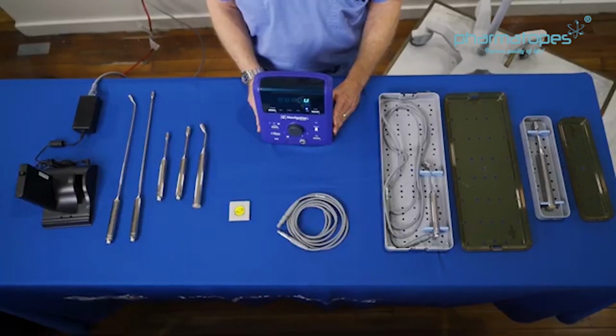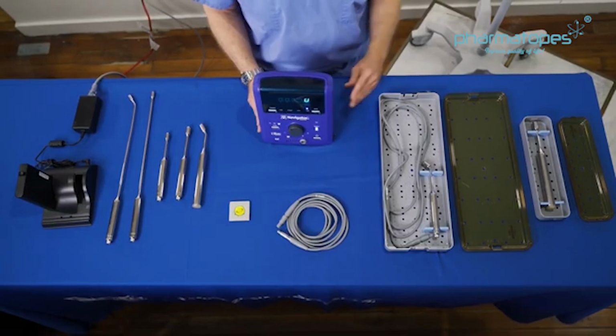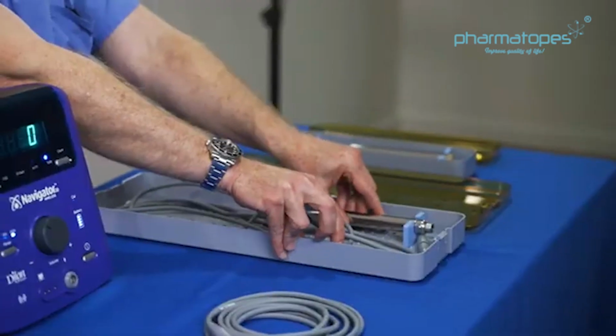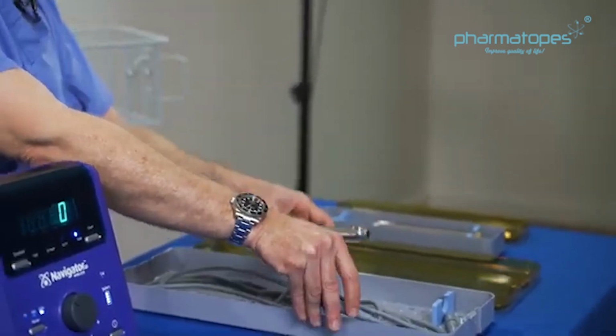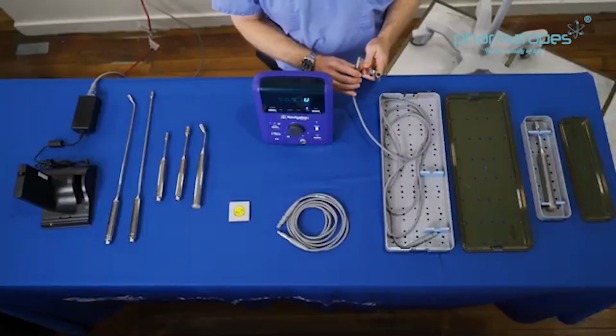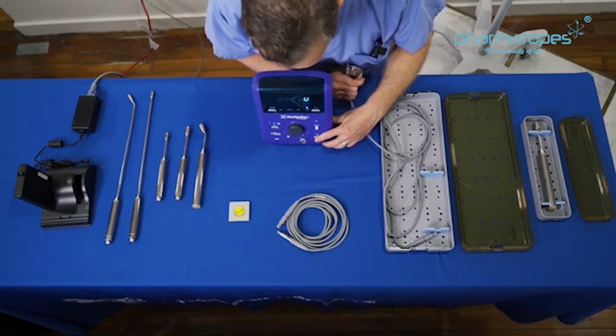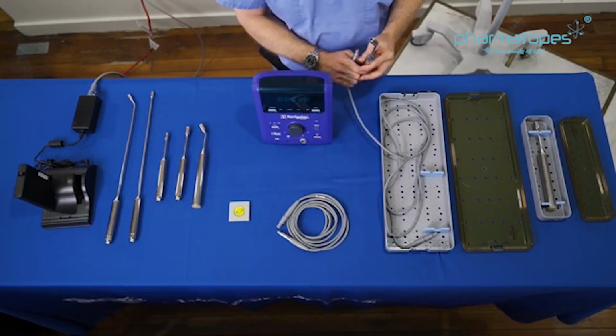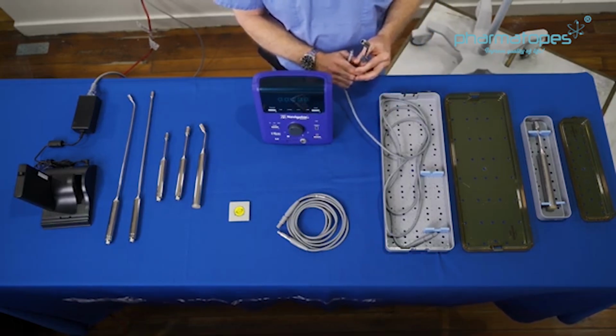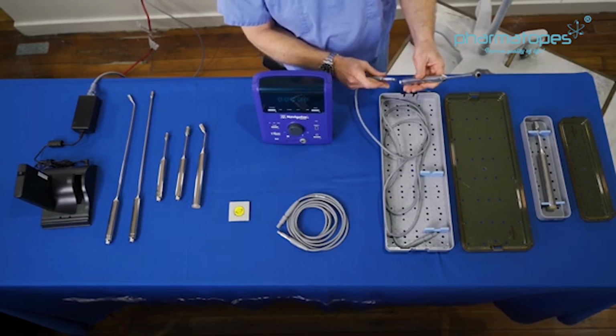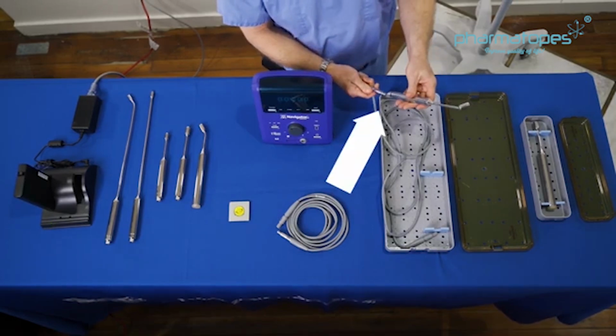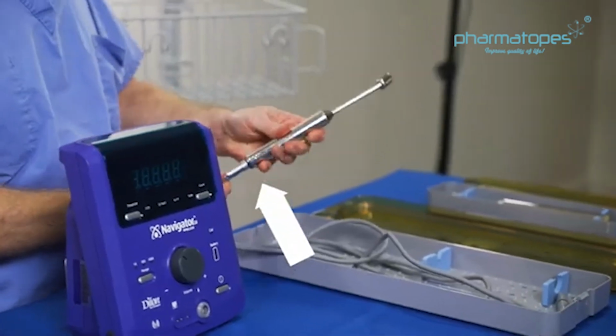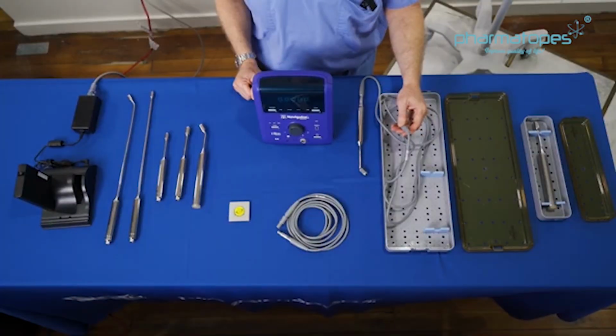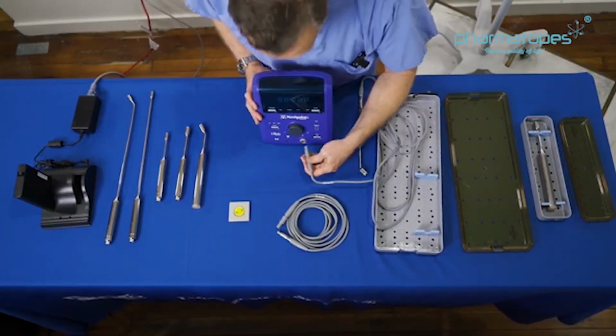The wired probe will typically come to the operating room in a sterilization tray. You remove the sterile probe and cable into the sterile field. Prior to connecting the probe to the control unit, make sure the control unit is off. First, connect the probe to the cable by making sure the red dots are aligned. Connect the cable to the control unit by making sure you align both arrows.